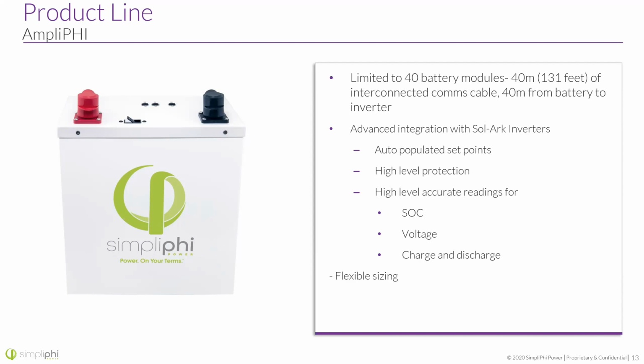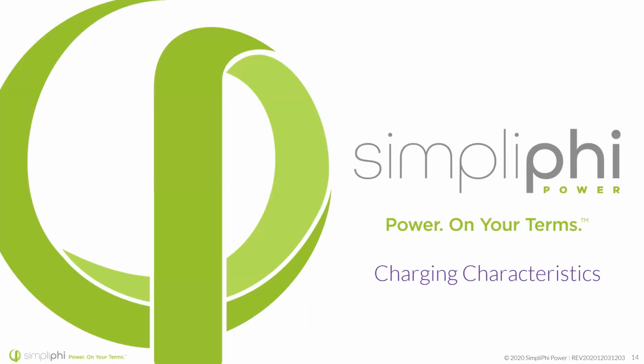If you're familiar with our sizing, we typically have a pretty strict rule when it comes to Phi batteries, the standard ones, where we want a 2-to-1 ratio, meaning if you've got an 8 kilowatt inverter, you want 16 kilowatt hours minimum of battery. In this case, you do not have that requirement, as the battery has its own protection built in to make sure that it's not over discharged, even if the inverter is too large. A little note on the side here, it is limited currently to 40 batteries in parallel when it comes to the AmpliPHI battery. All right, so that's products.